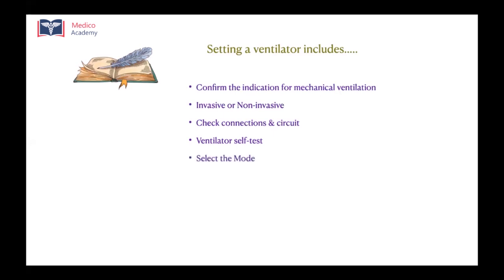Now, once that is over, the next step would be selecting the mode. Now the ventilator is ready to be used, right? You have checked the connections and circuit, and the ventilator has done a self-test. Now the next step is selecting the mode of ventilation. Once you select the mode, there'll be a lot of variables popping up on the screen. Now you set the variables appropriately. And once you set the variables, your next step should be to set the alarms so that there are no hazards caused by your mechanical ventilation to the patient.